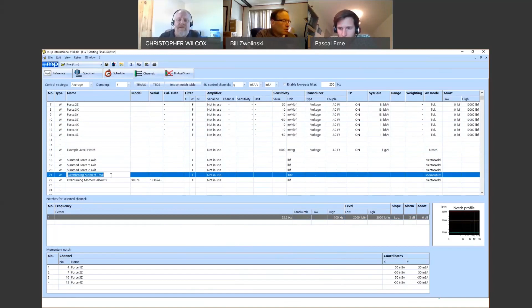Now, the next step up is overturning moment around an axis. So in this case, I made it simple. I put it 50 inches out on each side, and then I put a notch profile in. It actually won't hit this one. And then the more important, the overturning moment total. Here's where we have to enter both the X and the Y directions so that it can calculate the individual moments and then do a root sum square to give you the absolute overturning moment in case your CG is off center.